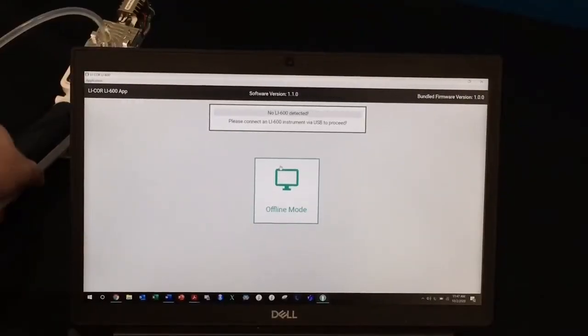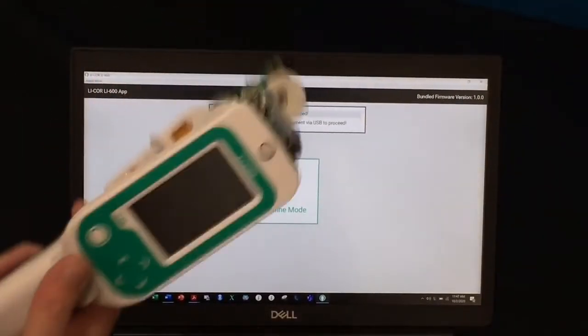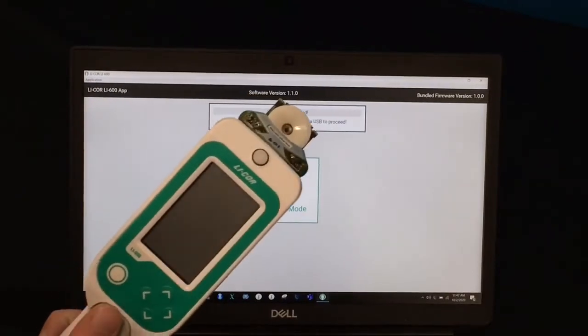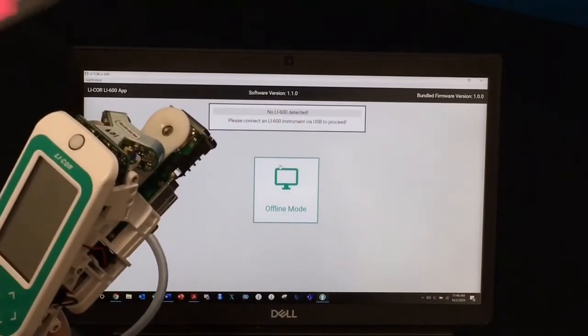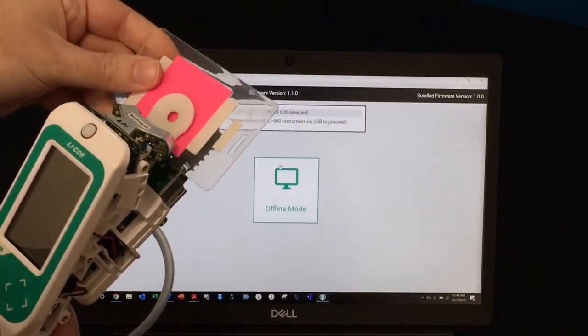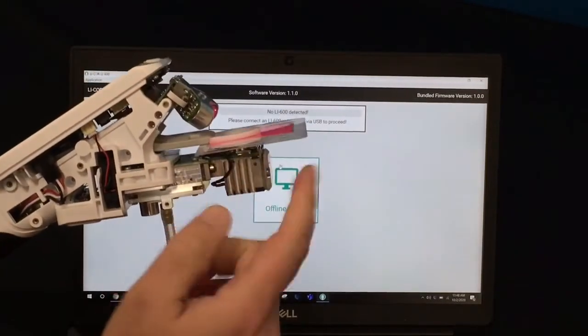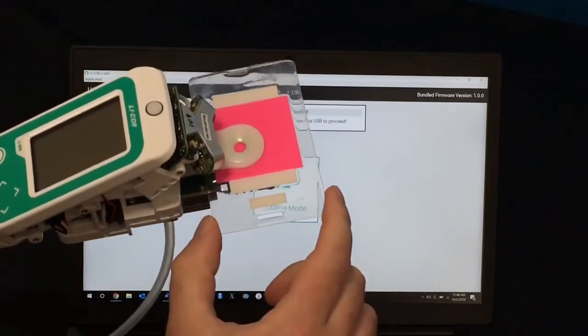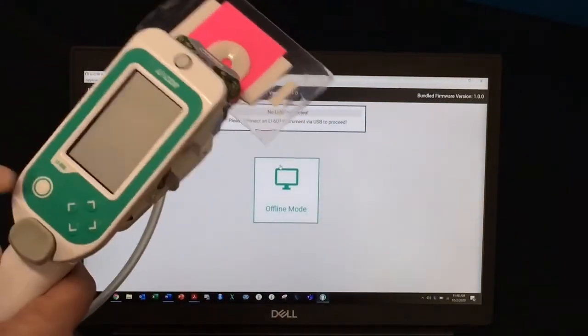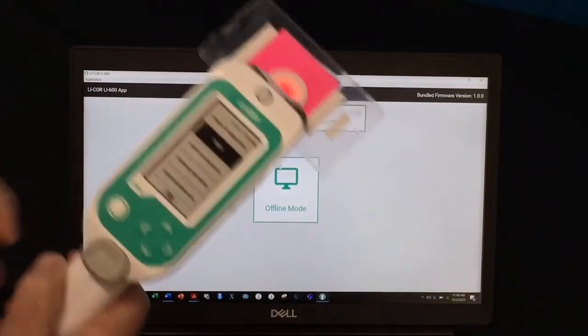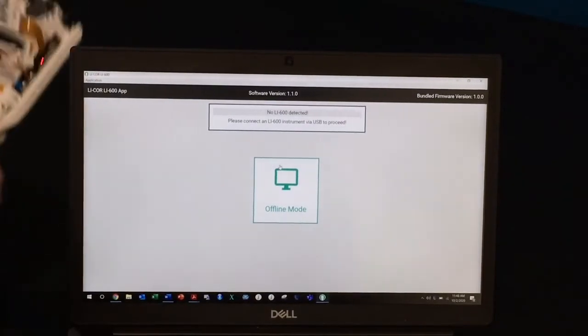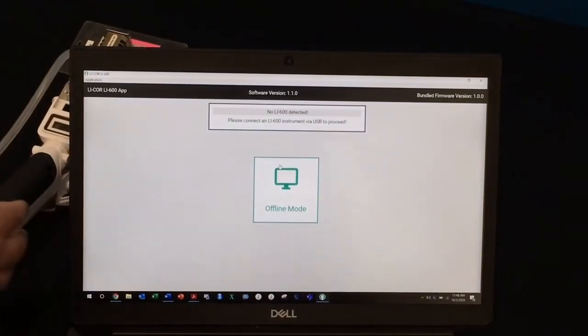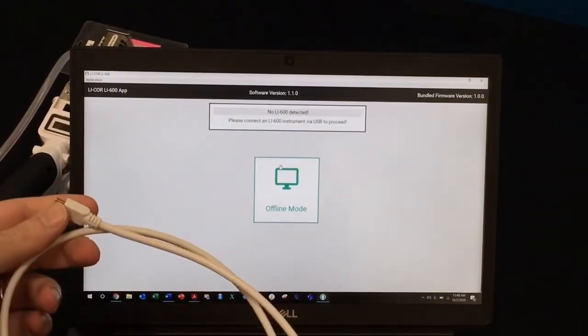The last thing you'll need to do on the hardware is to clamp on to a piece of plastic or laminated paper so that we get good airflow to both relative humidity sensors. Clamp onto the plastic just like you would any leaf and turn the instrument on. Then connect the instrument to the computer using the USB cable that came with the instrument.